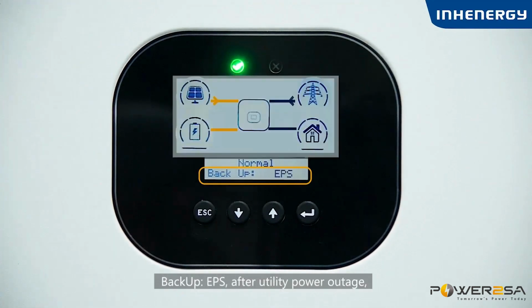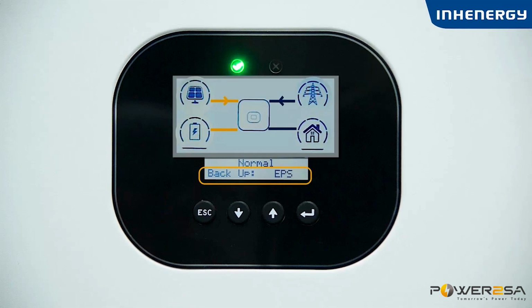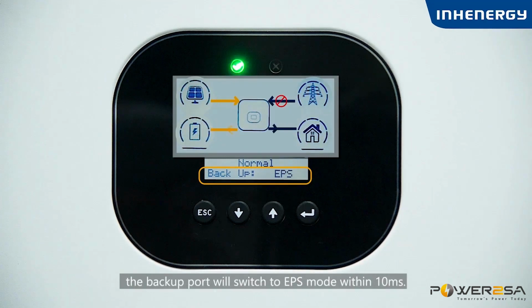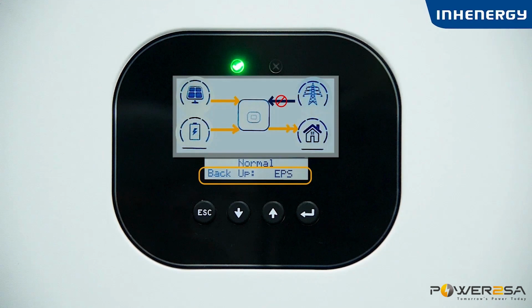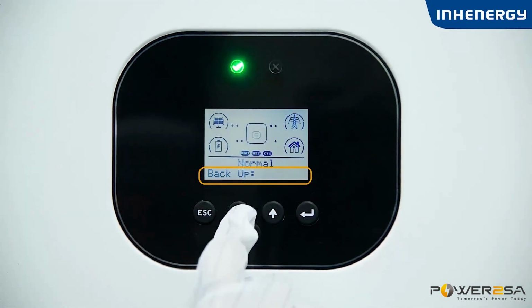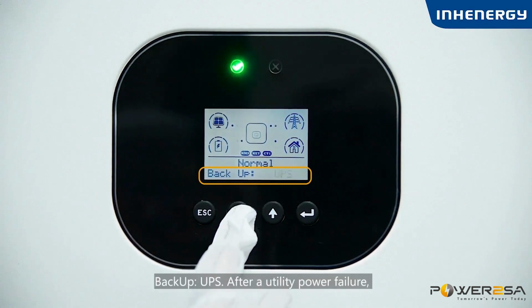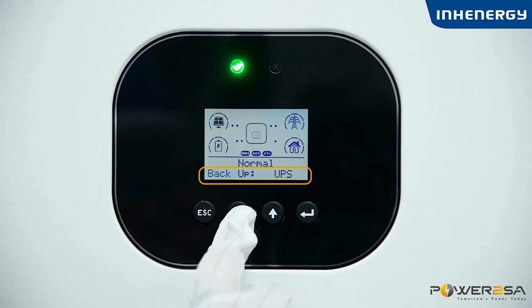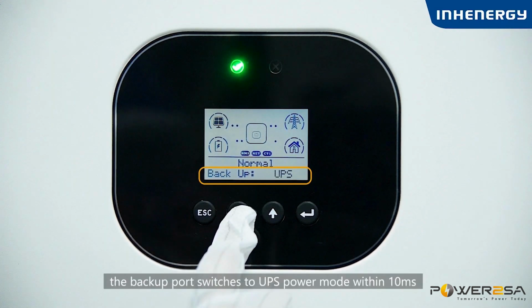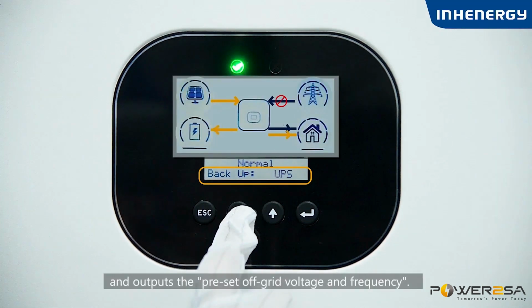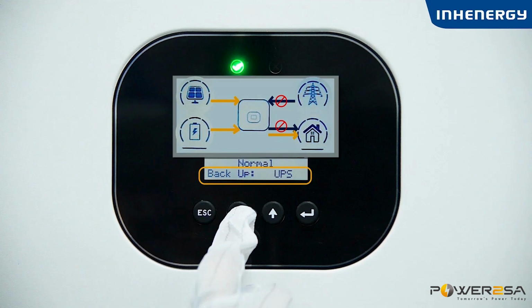Backup EPS. After utility power outage, the backup port will switch to EPS mode within 10 milliseconds. Backup UPS. After a utility power failure, the backup port switches to UPS power mode within 10 milliseconds and outputs the preset off-grid voltage and frequency.